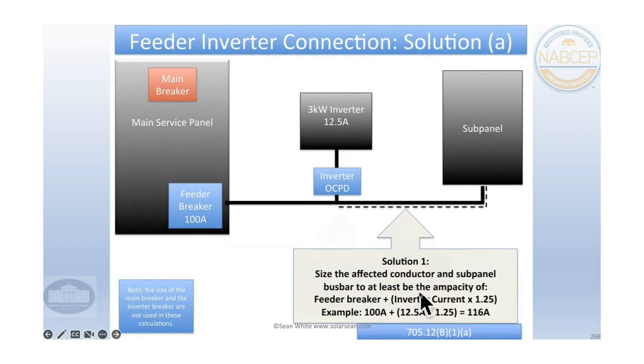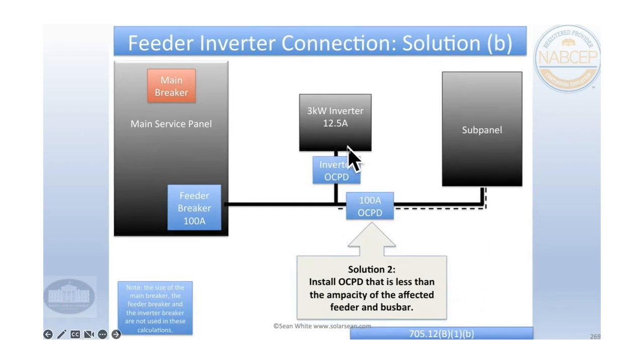So the first thing that you can do is make sure that this portion of the feeder between the inverter connection and the loads is at least the sum of the feeder breaker plus 125% of the inverter current. And if this portion of the feeder is not, which is probably going to be the case, you can put overcurrent protection on this feeder. And so that feeder breaker is 100 amps. So obviously 100 amps here would protect that.